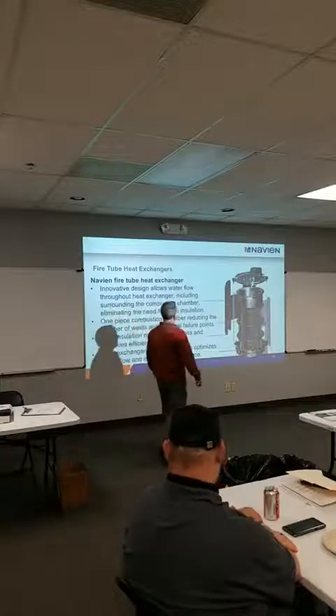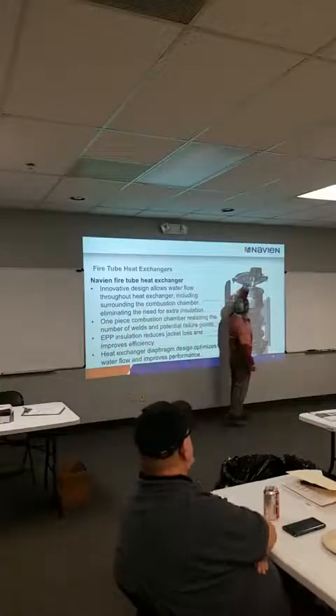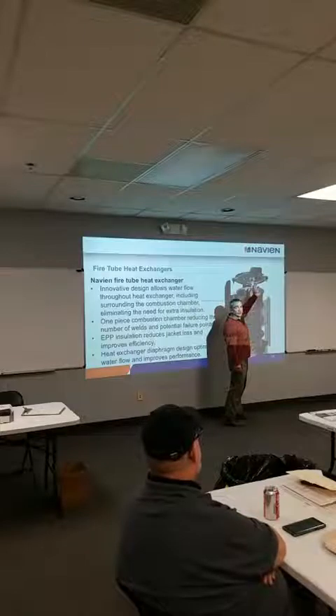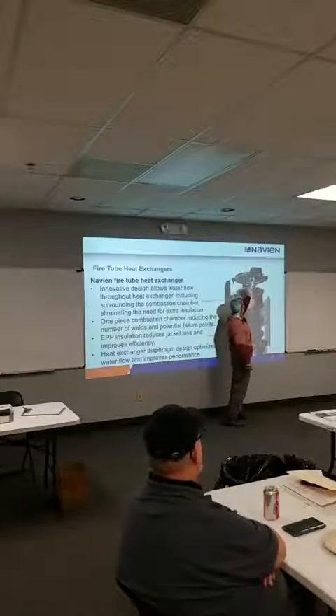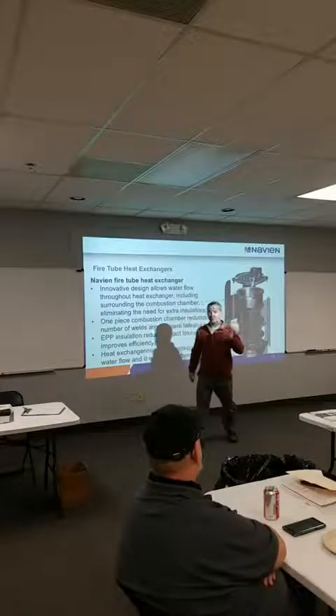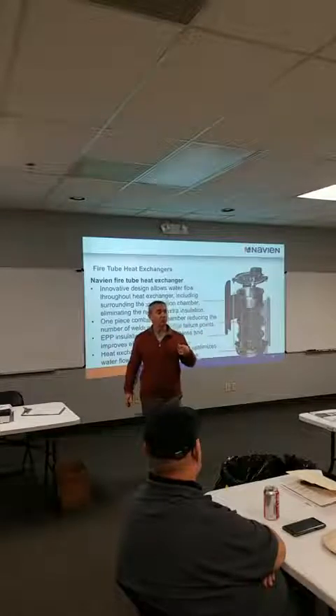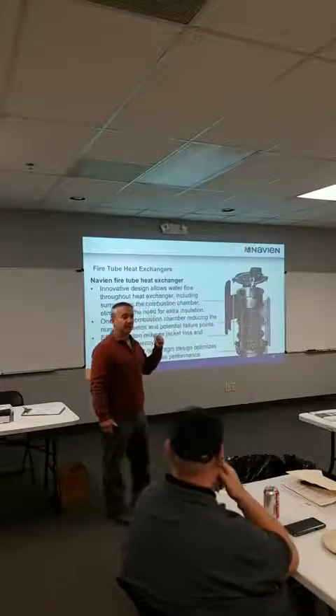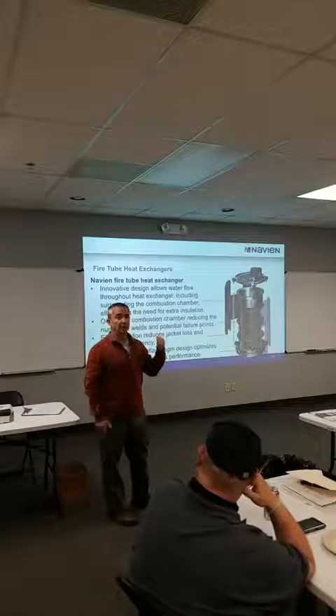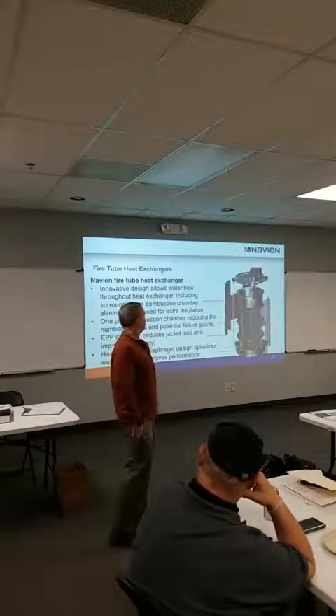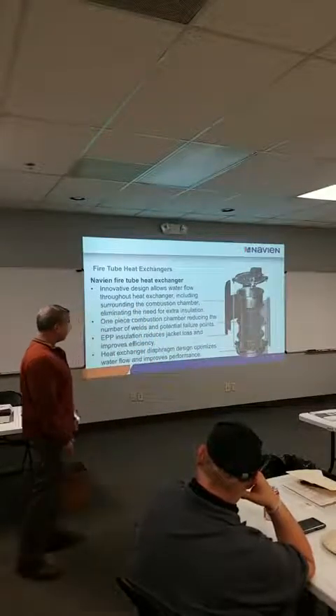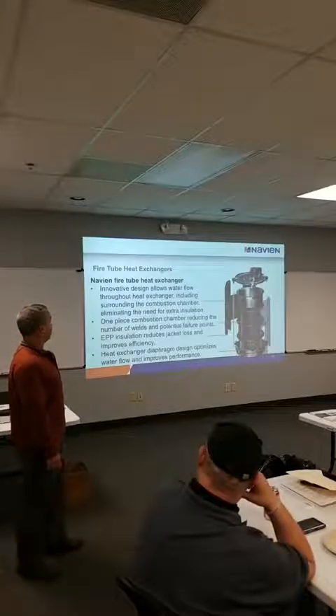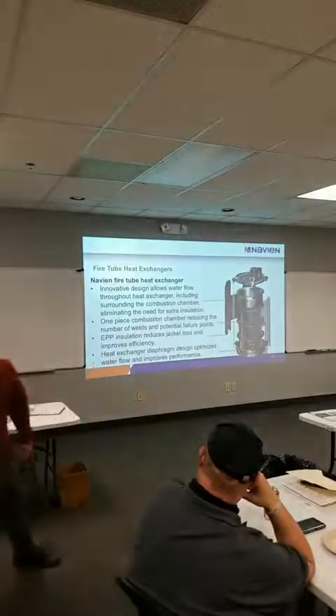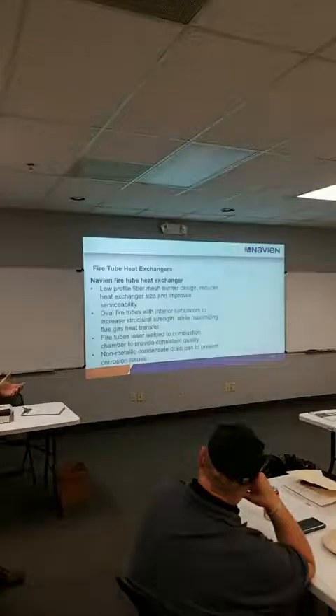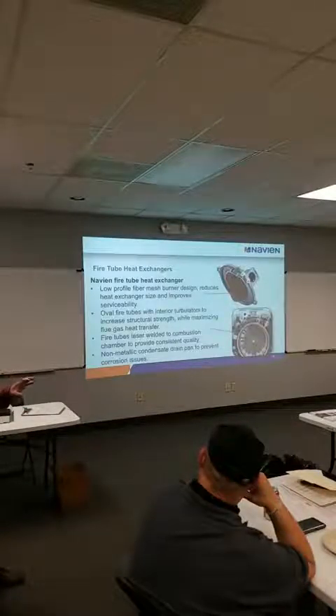Our flame rods are right here on top. This is very easy to access if you have to access it. Our burner assembly's on the bottom. They're telling me if you have a clean system going to this, you're probably never going to have to take the top of that apart and clean it, but I don't know if I necessarily buy that, but that's what they're telling us. So it's an insulated heat exchanger, it's all stainless steel. We make that product ourselves. We make all the fire tube heat exchangers ourselves, so it is all our product.